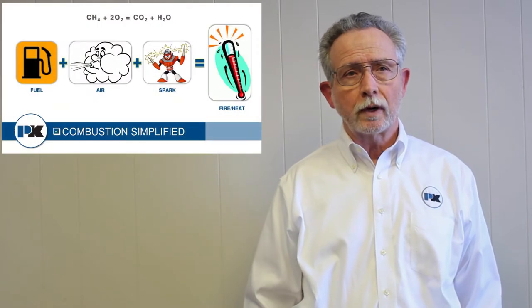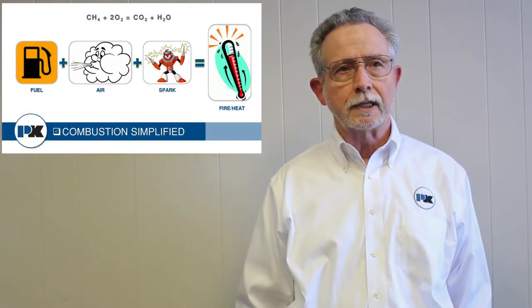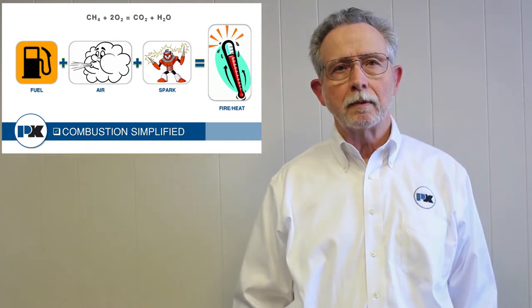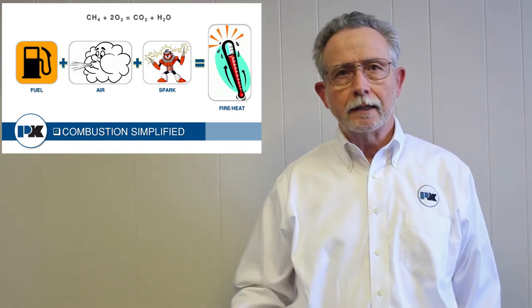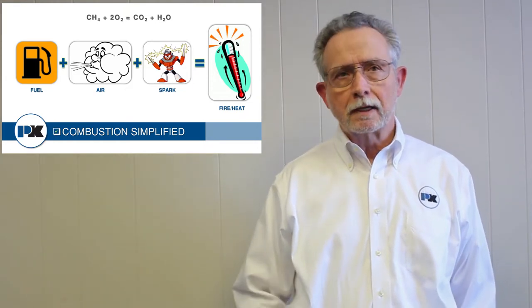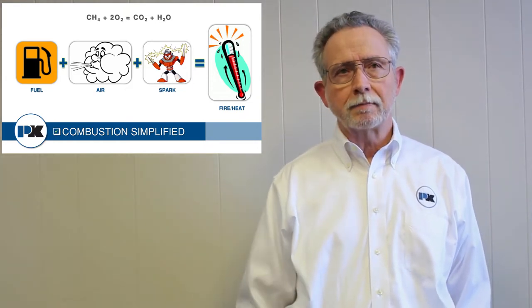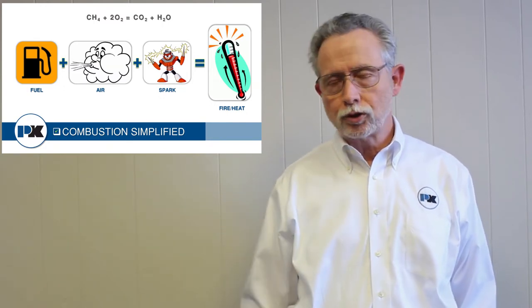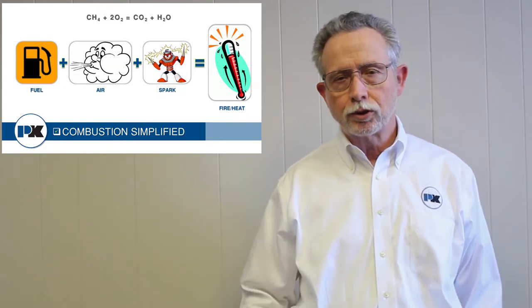First we're going to look at what's behind the turndown, and the first thing we need to understand is what is combustion. We're going to take fuel, add air, create a spark, and that gives us fire or heat. That's a very simplified version — basically natural gas plus a little O2 creates CO2 and water vapor.